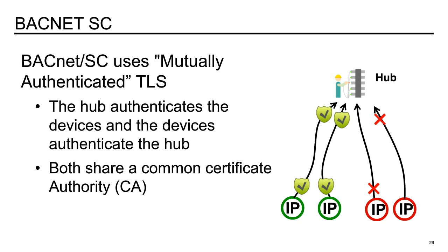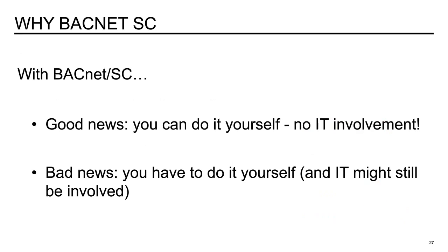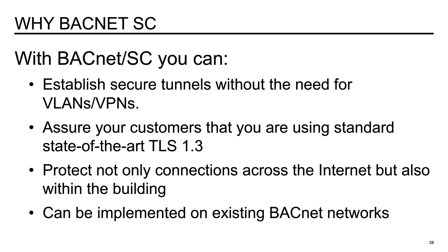So now you're probably asking, why BACnet SC? With BACnet SC, the good news is you can do it yourself. You don't have to have IT involvement. The bad news is you're still going to have to do it yourself, and IT might still be involved. With BACnet SC, you can establish secure tunnels without the need for virtual private networks or virtual local area networks, VPNs and VLANs. You're also able to assure customers that you're using standard, state-of-the-art TLS, and the current TLS is 1.3 today. You protect not only the connections across the internet, but also within the building. And then the really great news is this can be implemented on existing BACnet networks.